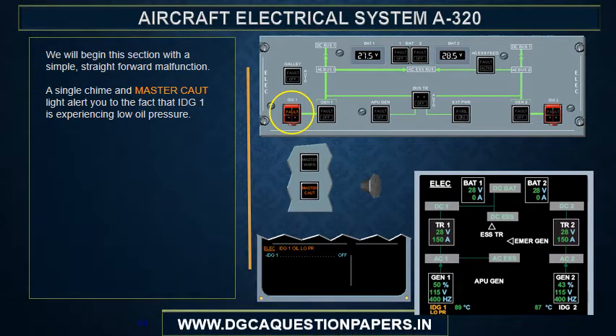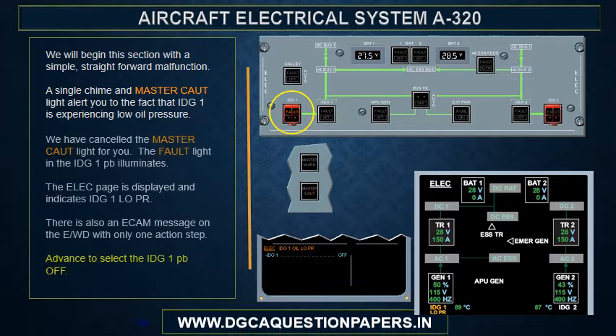We will begin this section with a simple, straightforward malfunction. A single chime and master caution light alerts you to the fact that IDG-1 is experiencing low oil pressure. We have canceled the master caution light for you. The fault light in the IDG-1 push button illuminates. The electrical page is displayed and indicates IDG1 low pressure. There is also an ECAM message on the EWD with only one action step.